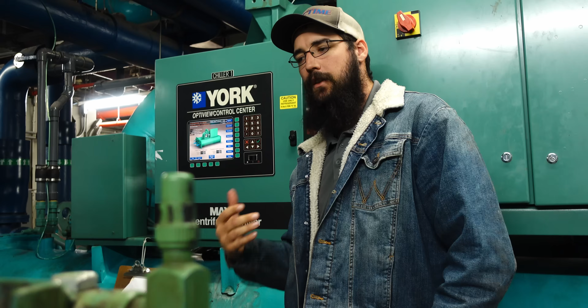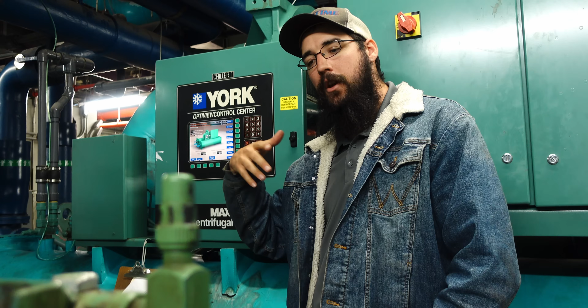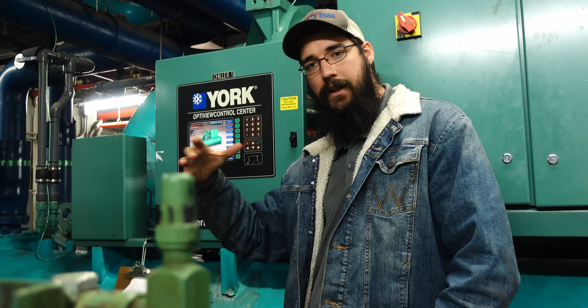At this point, there's not much else to do other than let it run. We're going to finish packing up. We'll let the customer know that she's doing her job. I'm not going to be able to calibrate the liquid level sensor until we have some legitimate load on this machine. So when we come back to do probably an annual PM in the spring, we'll plan to calibrate the liquid level. But I took it back to a default of 50%. This machine with the other sensor before it went bad was running a 50% set point and was spot on the condenser.